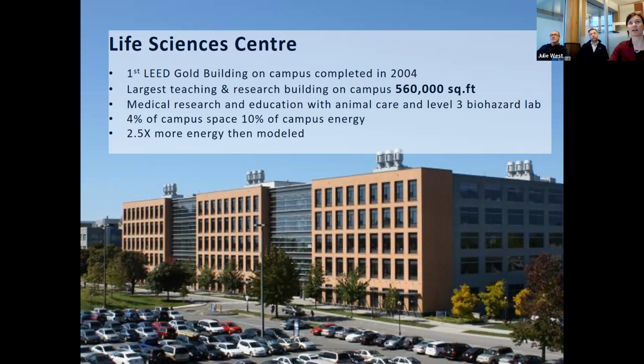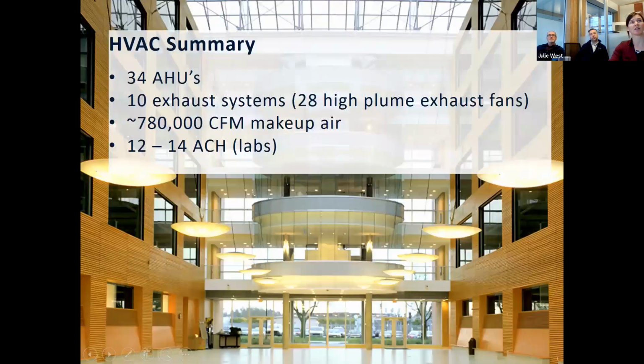It has an animal care area and a level 3 biohazard lab. It is roughly 4% of campus space and uses 10% of campus energy, and was using twice as much as modeled. HVACs: we had 34 air handling units, 10 exhaust systems, 28 high plume exhaust fans, around 780,000 CFM of makeup air. That's actually quite a bit light. It's more like 1 million. And 12 to 14 air changes in lab to begin with.